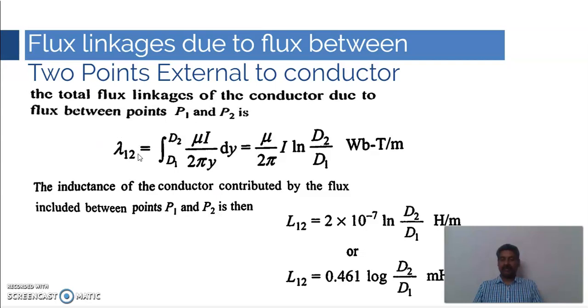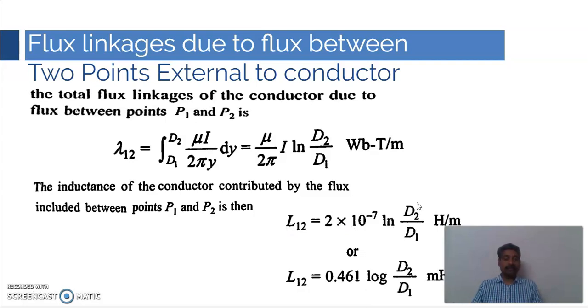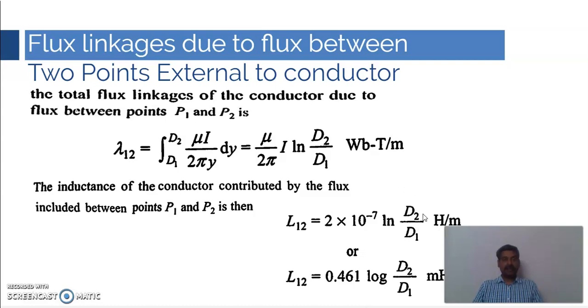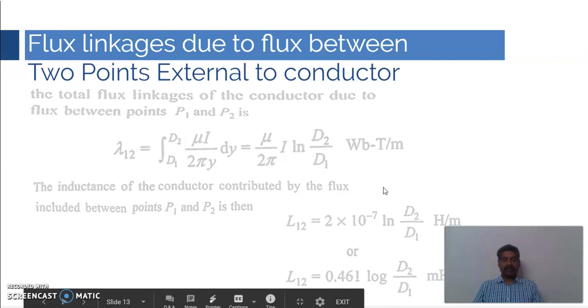Dividing the flux linkage by the current I gives the inductance. Substituting the value of μ and simplifying, the inductance contributed by flux between points P1 and P2 is L₁₂ = 2 × 10⁻⁷ × ln(D2/D1) Henry per meter. Converting to base-10 logarithm, this can be rewritten as L₁₂ = 0.461 × log(D2/D1) milli-Henry per kilometer. Note: natural log gives Henry per meter, while log base-10 gives milli-Henry per kilometer.